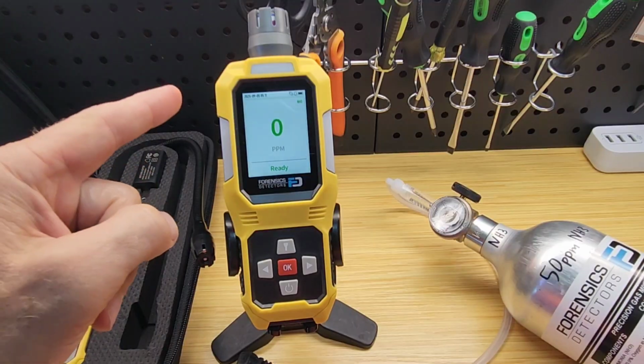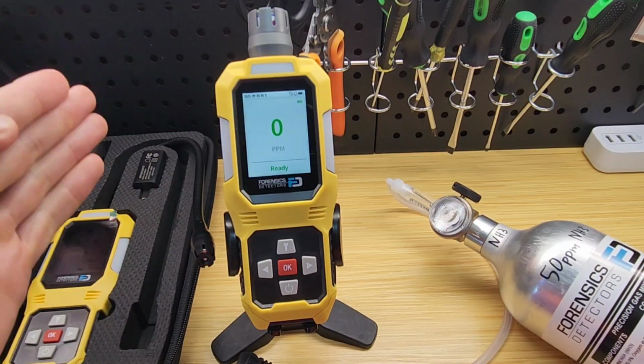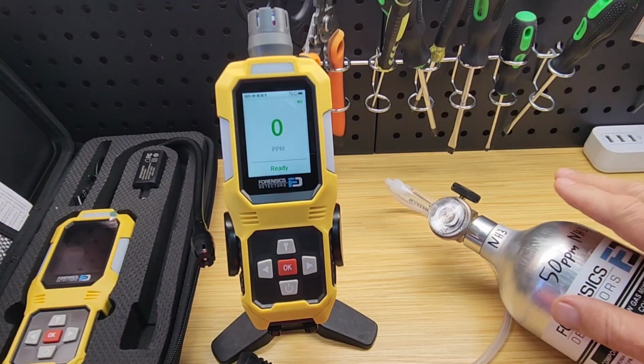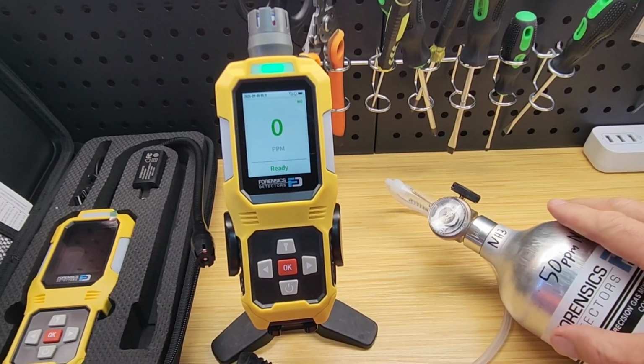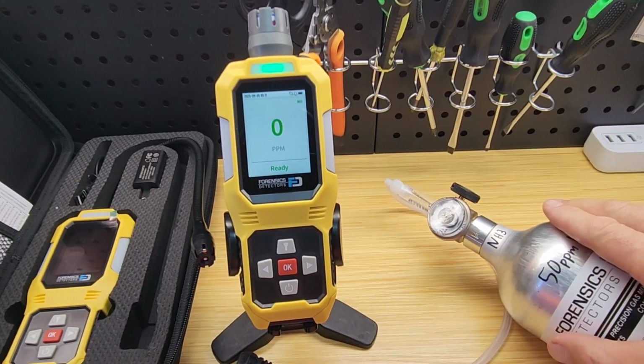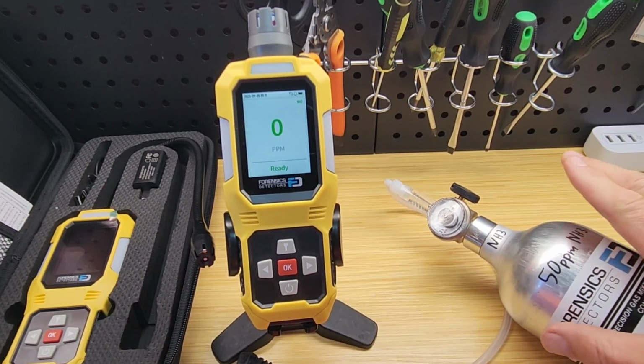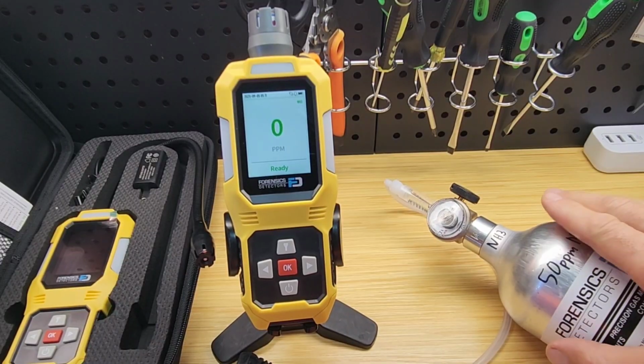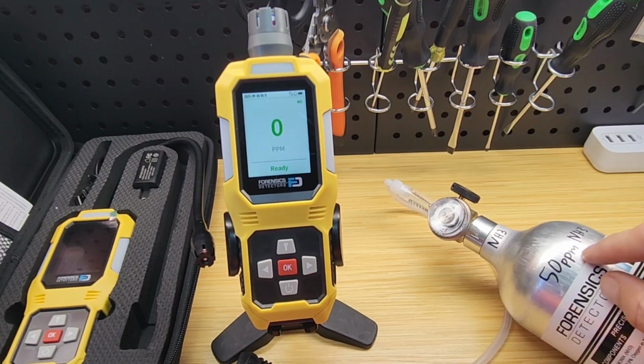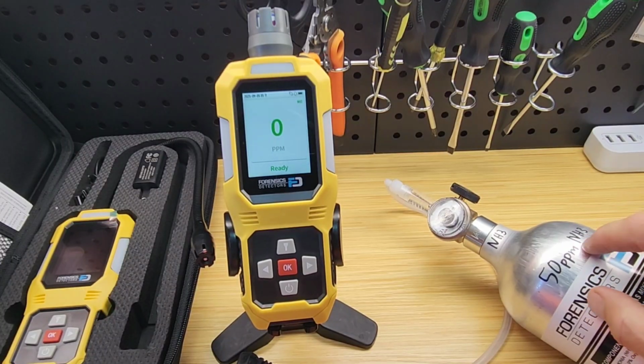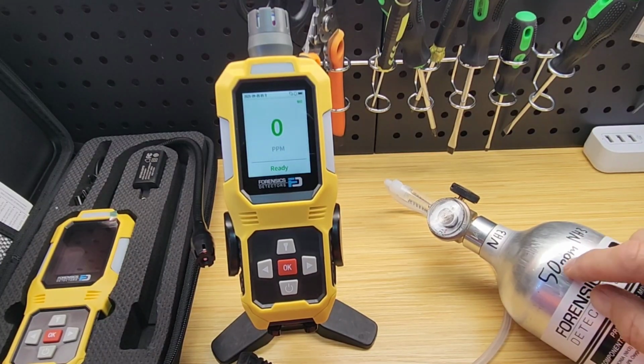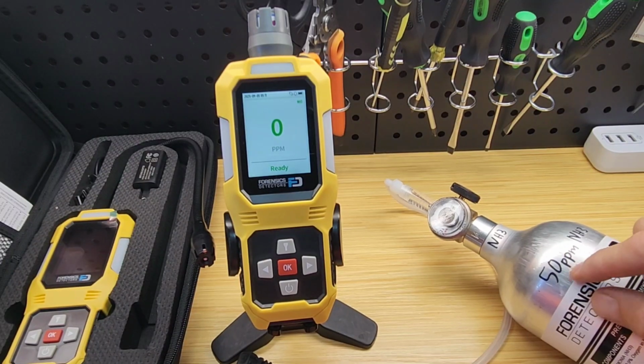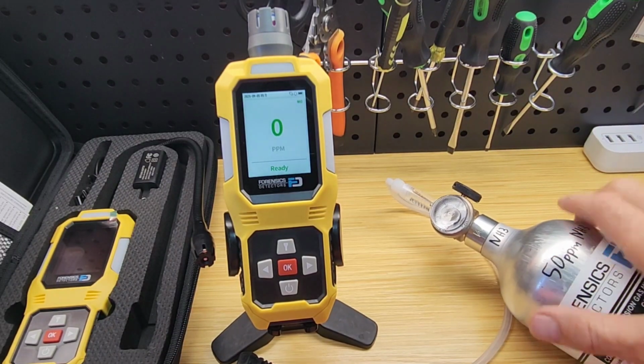Now, get your detector, turn it on, ready to go. For full calibration, we also need our reference gas that we have for each different model. We have an applicable reference gas that you will find, not only gas but also level. Today we are doing the NH3 ammonia, and our reference gas that's recommended by Forensics Detectors is 50 parts per million. This is the gas bottle.